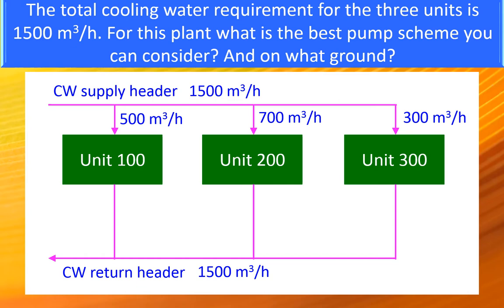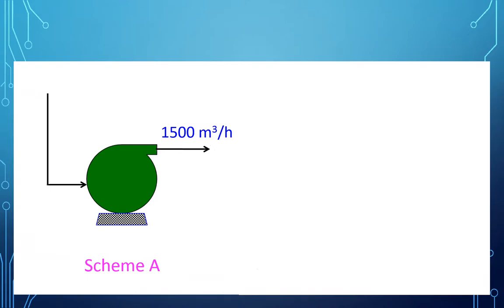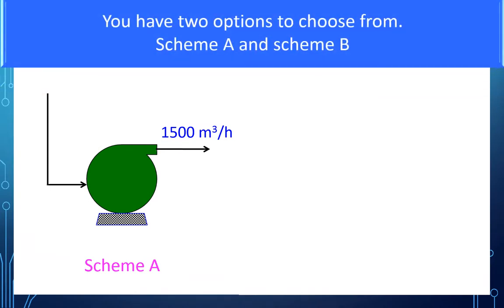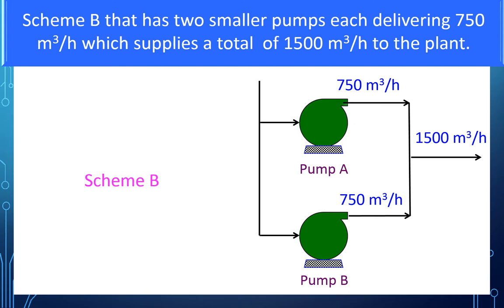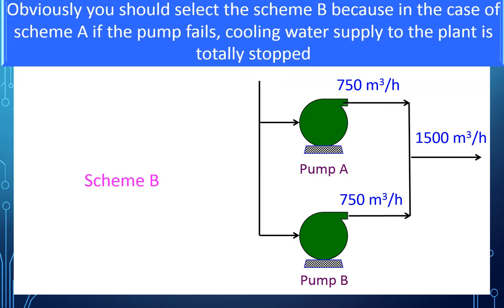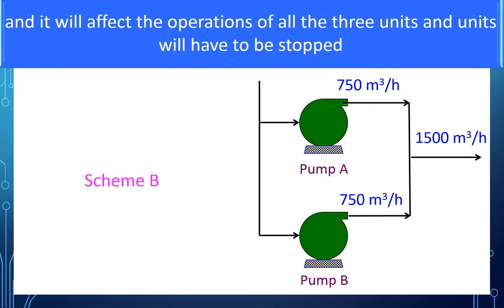For this plant, what is the best pump scheme you can select and on what ground? You have two options to choose from, scheme A and scheme B. Scheme A has a single pump delivering the total flow of 1,500 cubic meter per hour. Scheme B has two smaller pumps, each delivering 750 meter cube per hour which supplies the total of 1,500 cubic meter per hour to the plant. Obviously, you should select the scheme B because in the case of scheme A, if the running pump fails, cooling water supply to the plant is totally stopped and it will affect the operation of all the three units.